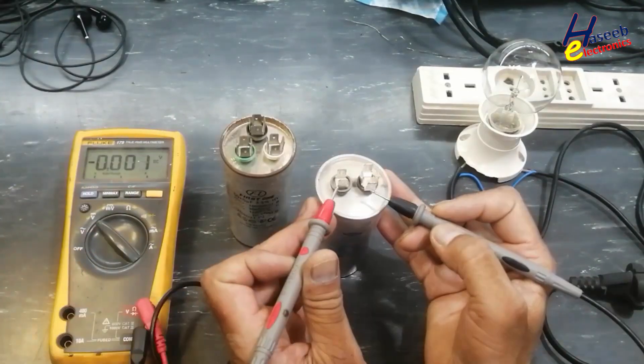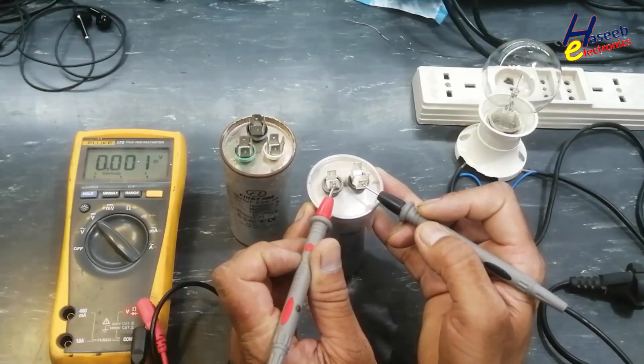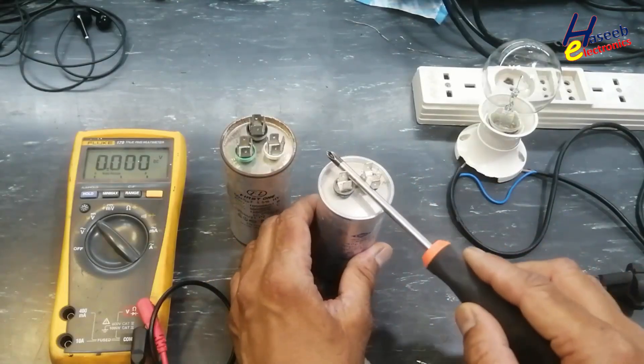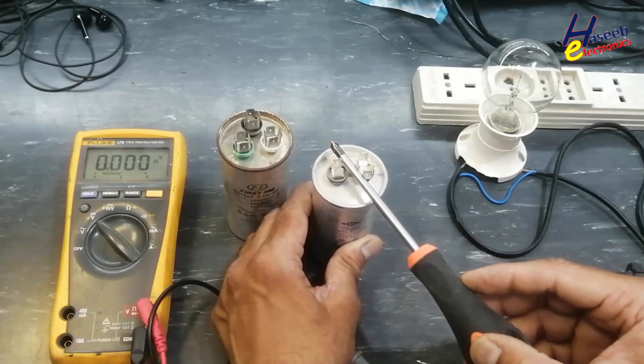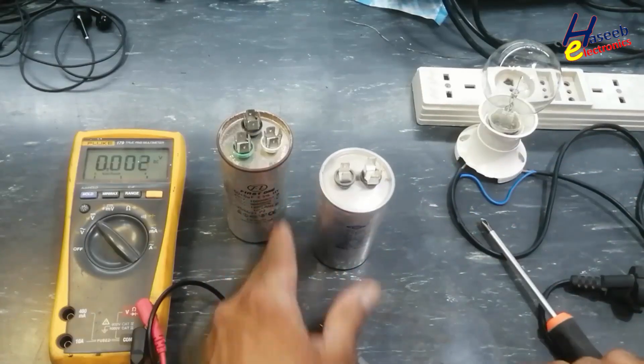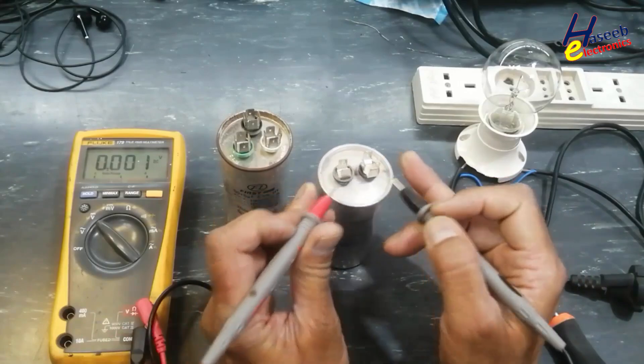Set multimeter to DC voltage, connect to both input terminals. If there is voltage, we will discharge it. Jumper both terminals of the capacitor using screwdriver, never touch metallic part of the screwdriver. Then check voltage, 0V.